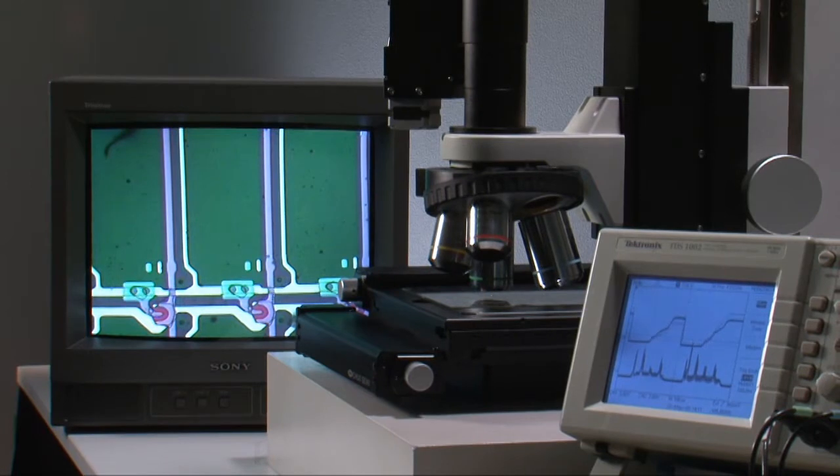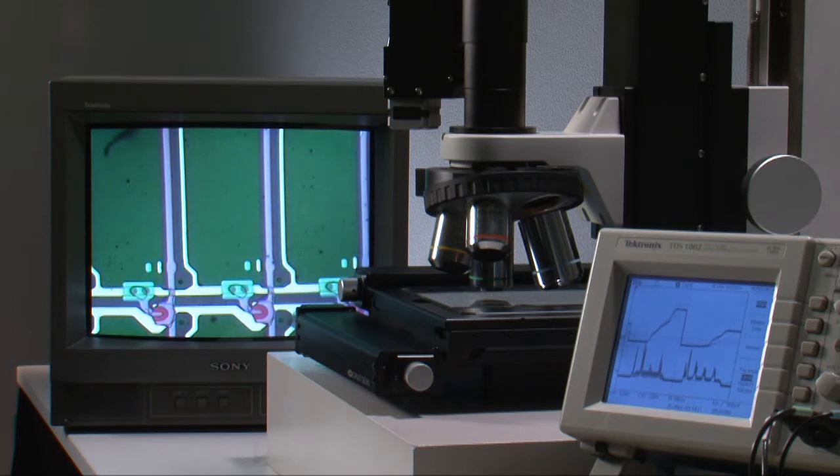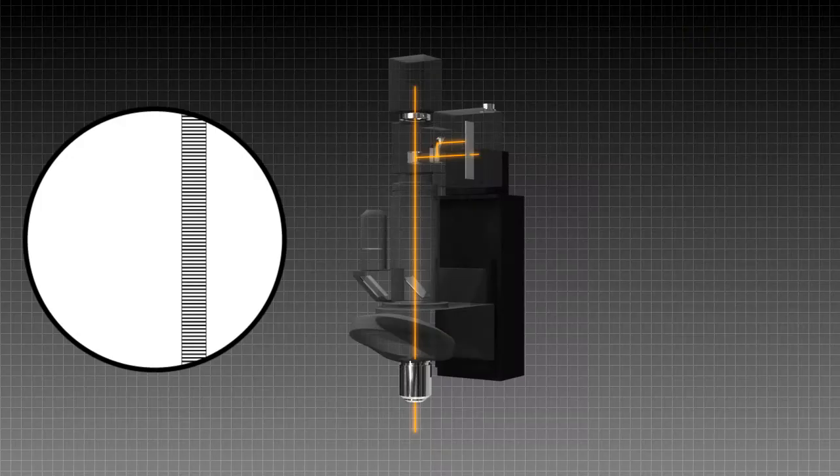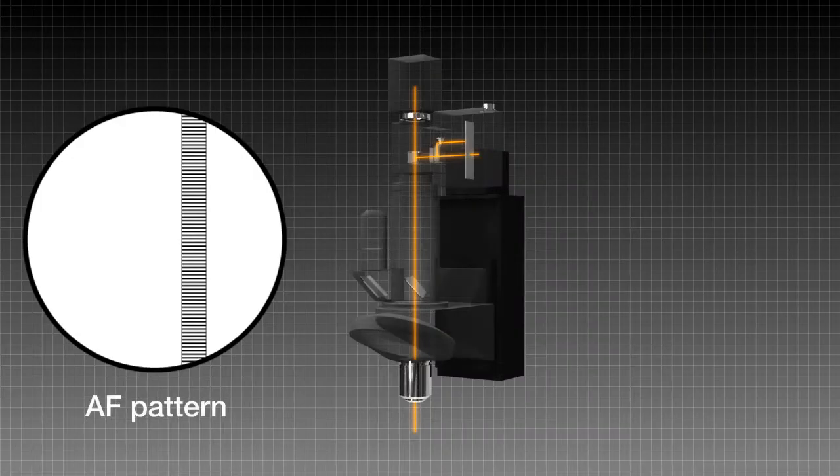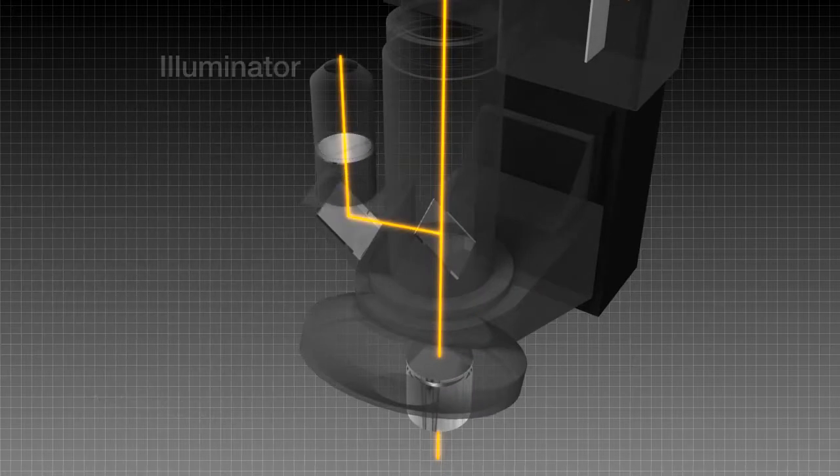However, with an unsteady video signal coming from the image of the target object, the line sensor cannot function properly, so a stripe pattern is projected to autofocus. This stripe pattern is projected by the AF pattern filter, positioned at the field stop in the illuminator section.